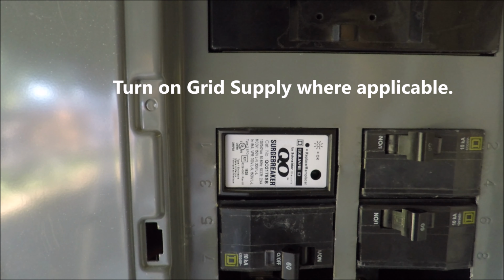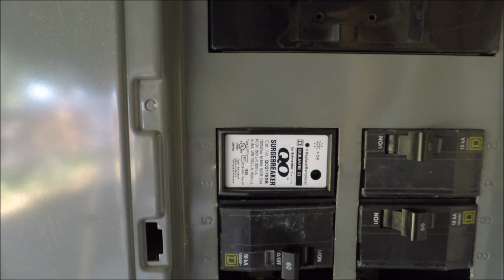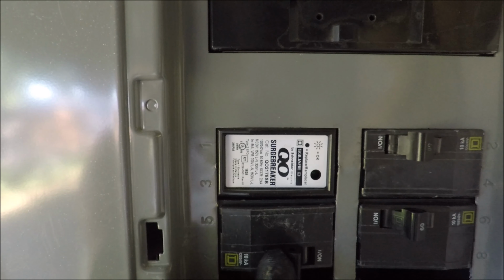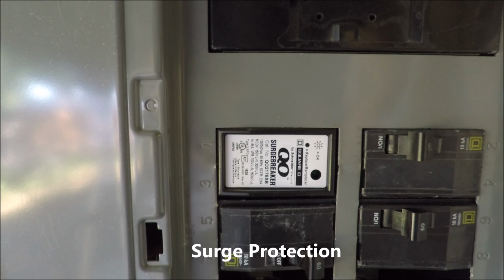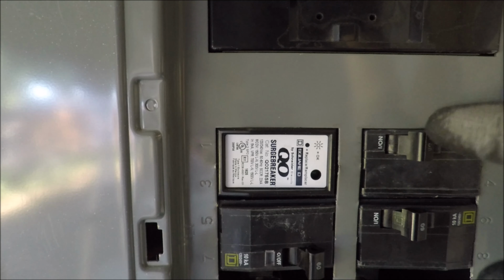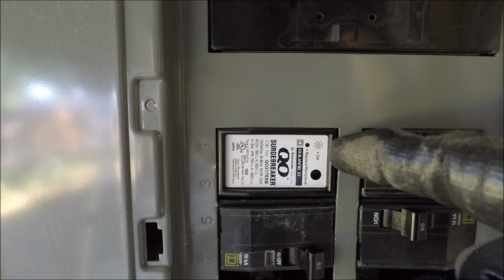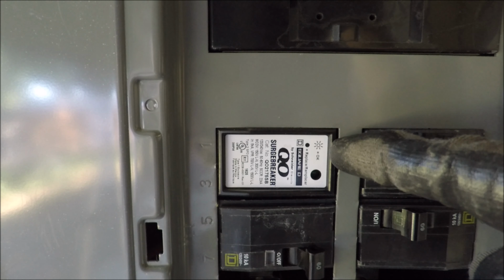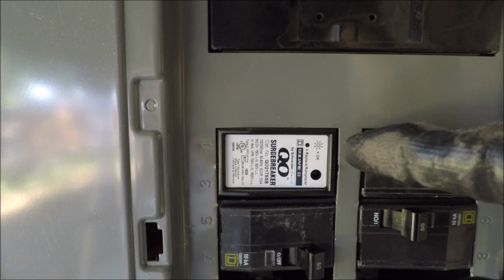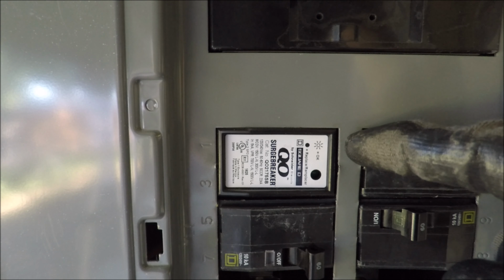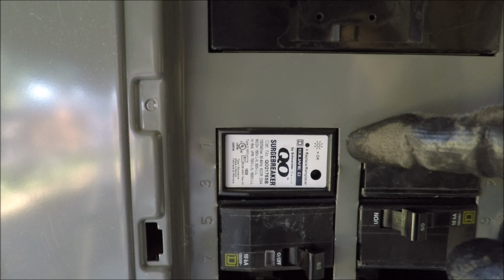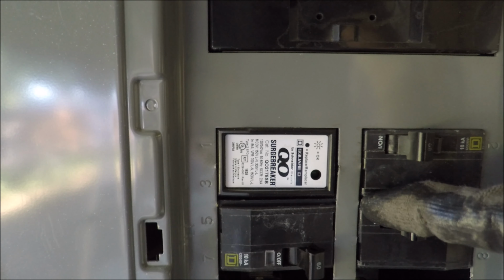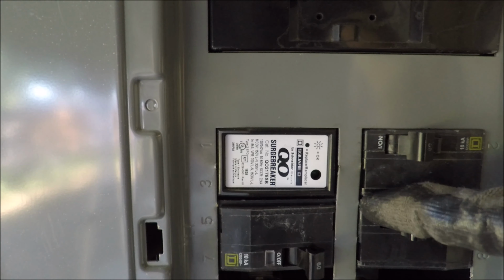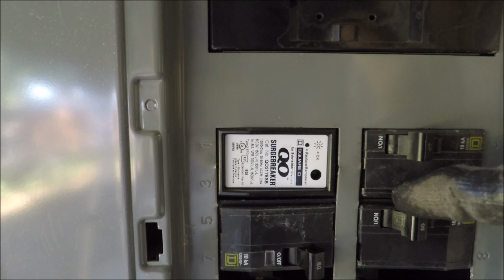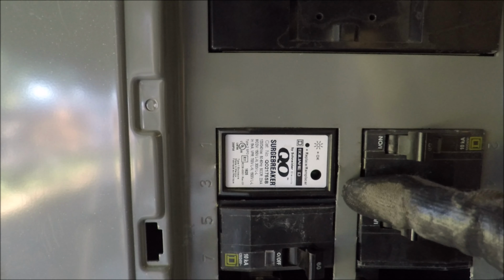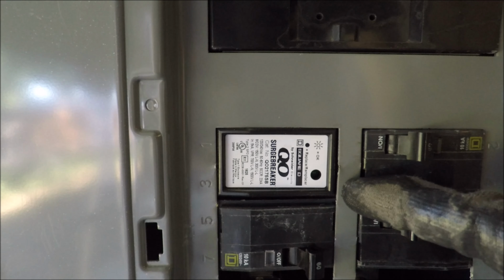The next step, if your inverter is grid tied, you want to turn on the grid supply breaker. Also, a tip, most breaker panels, the manufacturer will make a surge protection device. This is a Type 2 surge protection device that I have installed in the panel and connected to the neutral bar. This protects all the devices in this panel from surge instead of having to put individual surge protection devices on each one of my devices down the line. These are about $40 to $60 online and on eBay.